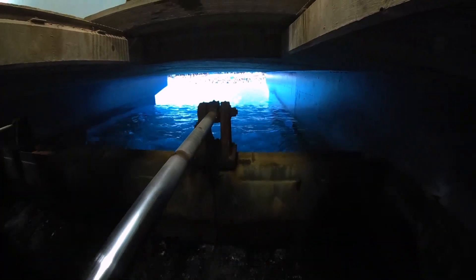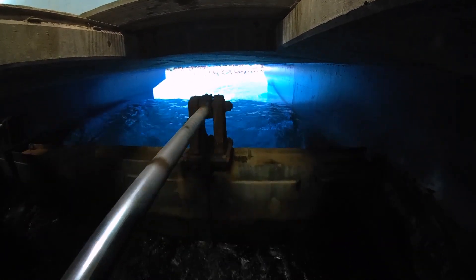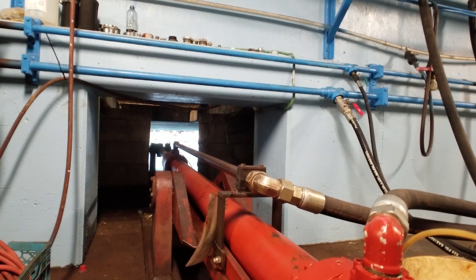But that hasn't been the system's only hiccup. The amount of force put out by the system to push those panels is so powerful that over time, the original rods actually needed to be modified. Today the shaft looks noticeably larger, but the original versions were only about two-thirds as thick. The force of the system bent them like spaghetti — they weren't strong enough to take the force required to make the waves — so this led to their current, stronger version.